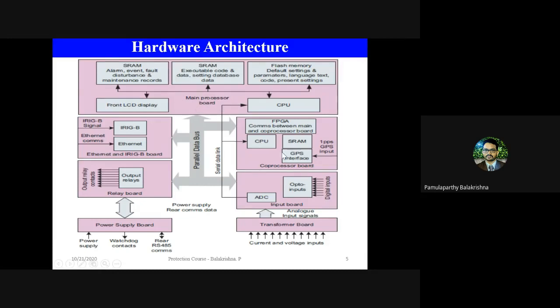And the coprocessor board, or the second processor, is majorly responsible for handling the communications. Okay, so in the context of the smart grid, communication is very, very critical for any component or any device. So a variety of communication mechanisms and protocols are supported. All those communications are handled by a dedicated second processor, which talks to the sensors downstream of the relay, or the upstream SCADA or substation HMI, those kinds of things, which act as a master station to this relay.